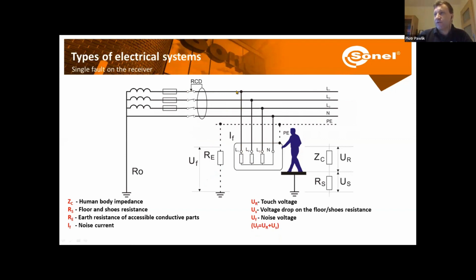Well, we're gonna have a current flowing through a phase channel to our device. And because of a fault over here, we're gonna have some potential on the cover of the device, which is going to be led to the earth through the protective channel. So through the PE channel to the earth, either directly to a transformer like in TN systems, or in TT through the actual ground. Or in case some unlucky person is touching the cover of this device, well, then the current will flow through their body and to the earth.